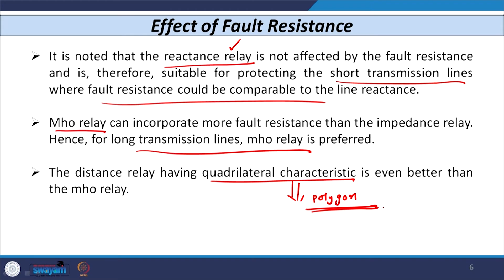If I consider the Mho relay on the other hand, then the Mho relay can incorporate some significant value of fault resistance compared to the impedance characteristic and reactance. So, it can be used for protection of long transmission lines. If I consider the quadrilateral characteristic, then it is even better than the Mho relay. Other characteristics like lenticular or quadramho are still better than the quadrilateral characteristic. Nowadays they are using a characteristic known as polygon. So, this is also one of the applications of this type of characteristic for protection of long lines.